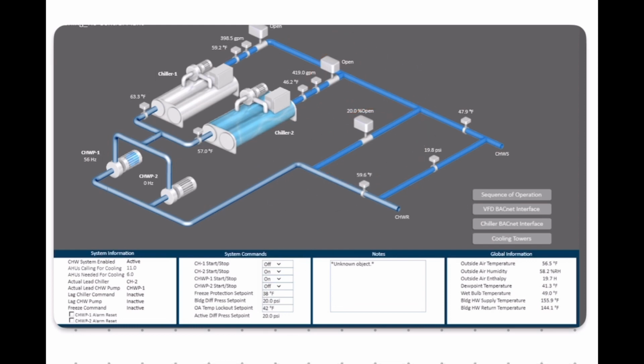I'm gonna show you again how the water cycle works from your air handlers. It comes through here. That's coming from your air handler. It goes to pump number 1, and now it goes to chiller number 2. It goes to your evaporator. You cool down the water, and now it goes out from your evaporator into the building, and that will be your supply to the building. You also have your bypass, and your water runs through here on this line, and then it goes back to the chiller. In this case, only 20% of the valve is open. So this is it for the cooling side of the chiller.